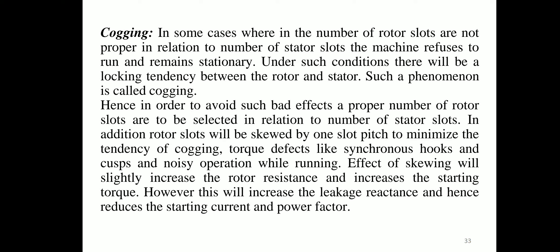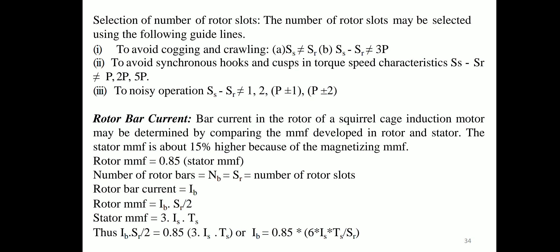Skewing slightly increases the rotor resistance and increases starting torque, but also increases leakage reactance, reducing starting current and power factor. Guidelines for selecting rotor slot numbers: (a) To avoid cogging and crawling: Ss ≠ Sr, and (Ss − Sr) ≠ 3p. (b) To avoid synchronous hooks and cusps: (Ss − Sr) ≠ p, 2p, or 5p. (c) To avoid noisy operation: (Ss − Sr) ≠ 1, (p ± 1), or (p ± 2).